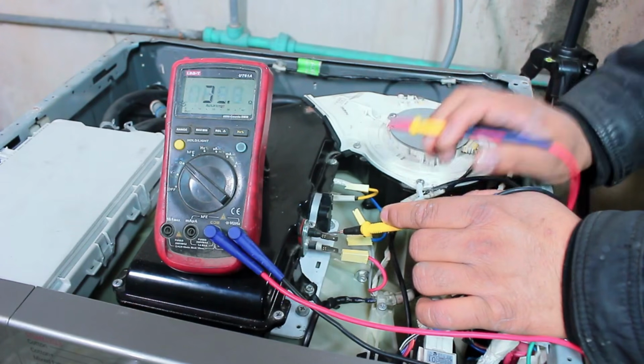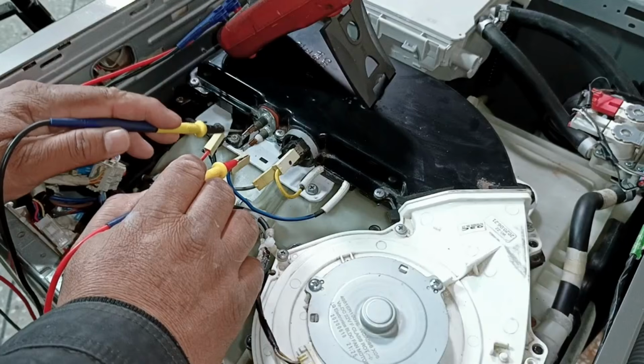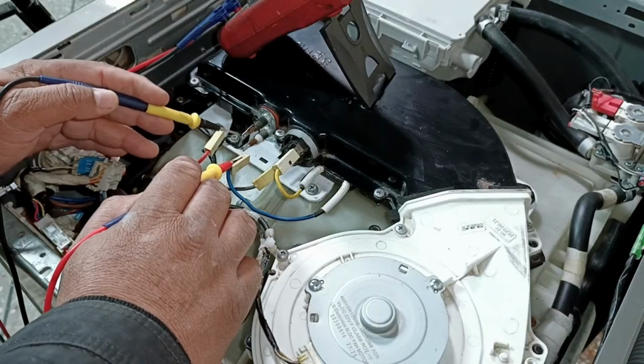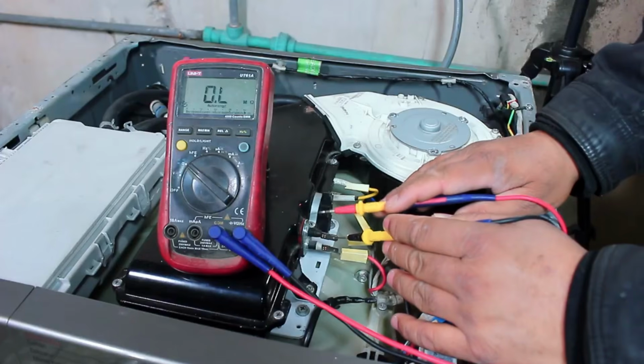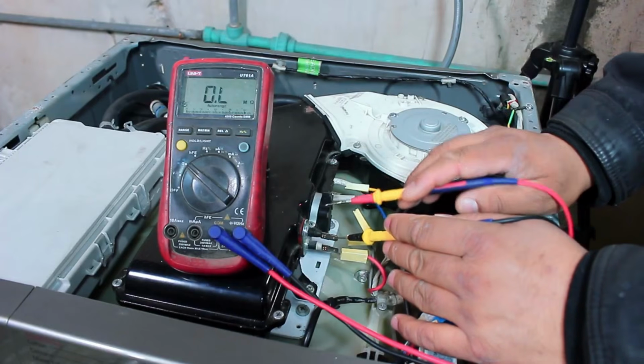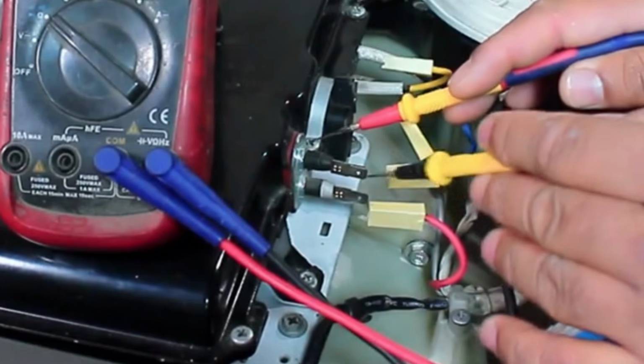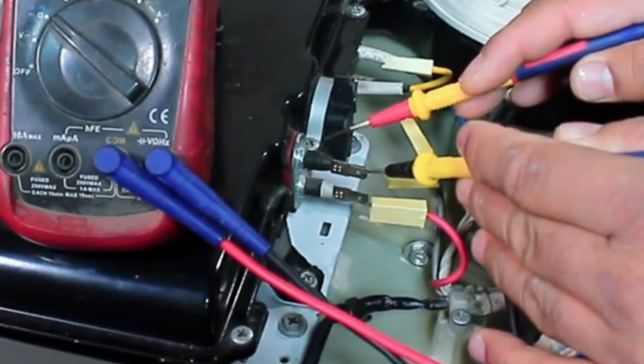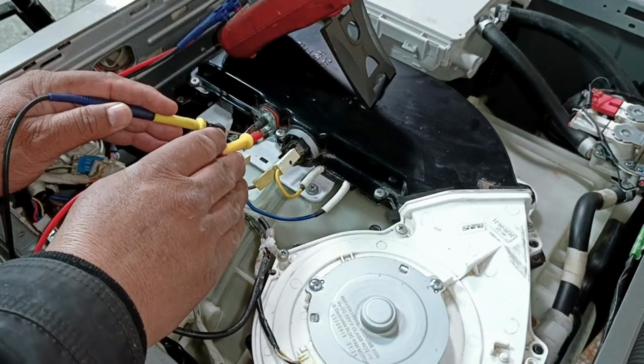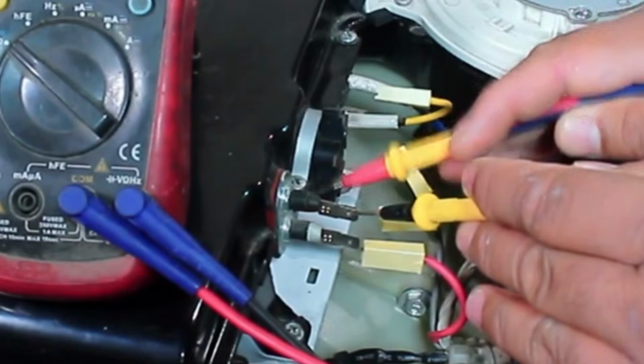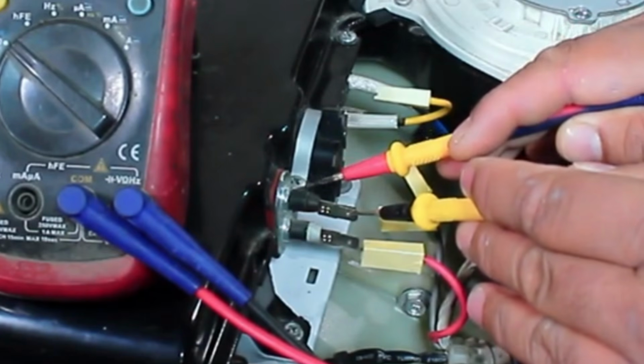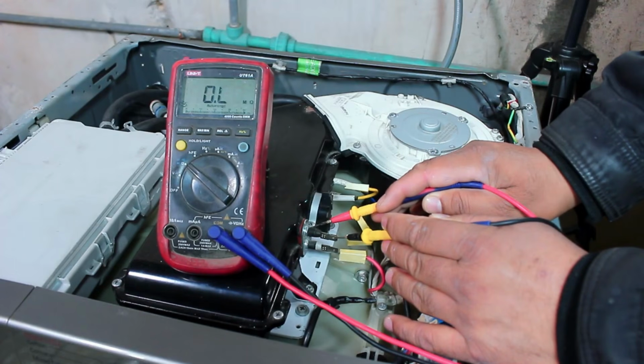Besides this, there is one more very important test. What often happens is that when the heating element is cold, it does not show any issue. But when it heats up, that's when the problem can appear. So for that, a body insulation test is very important. As you can see, I placed one probe here on the terminal, and the other probe on the metal body of the heating element. There should be no resistance reading between them.